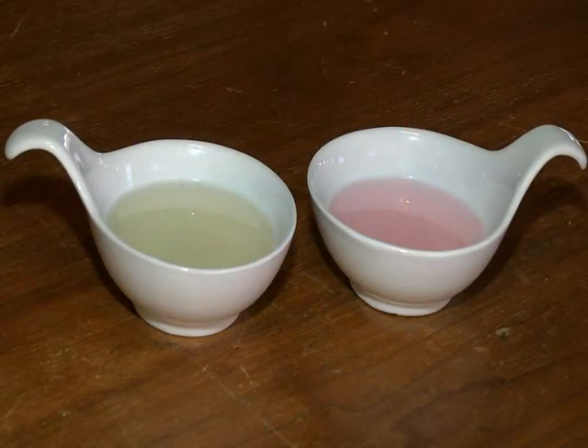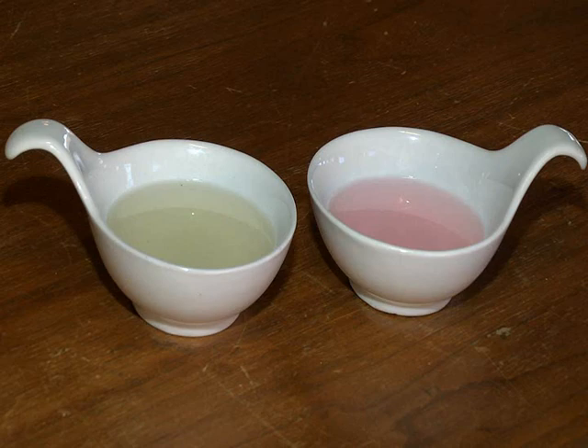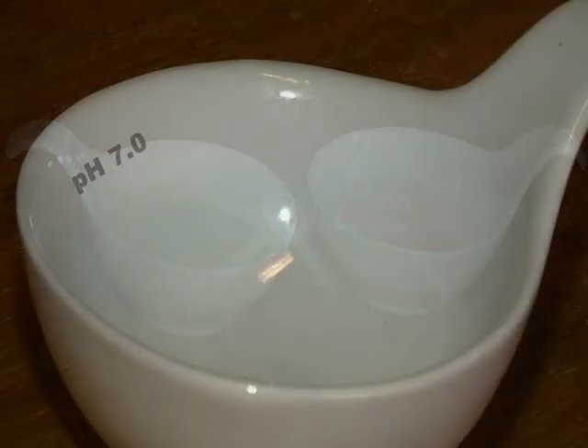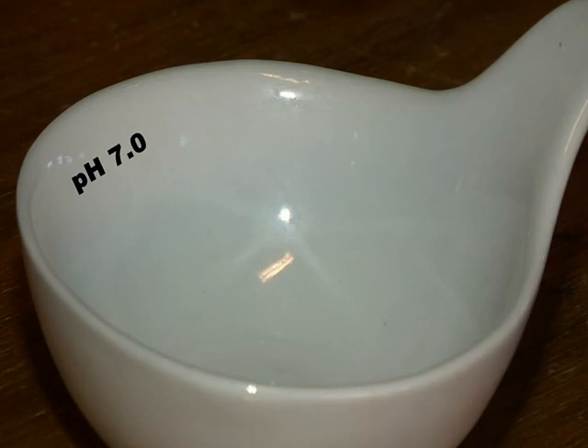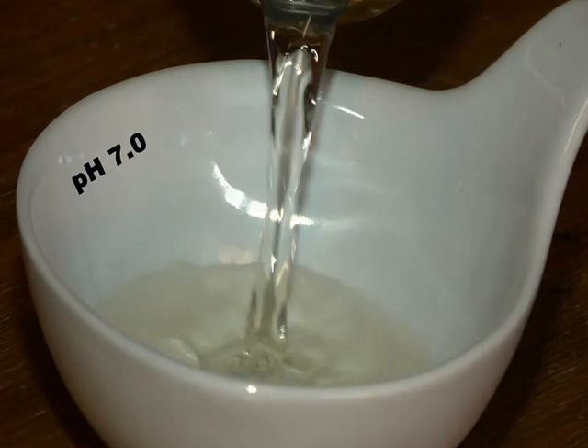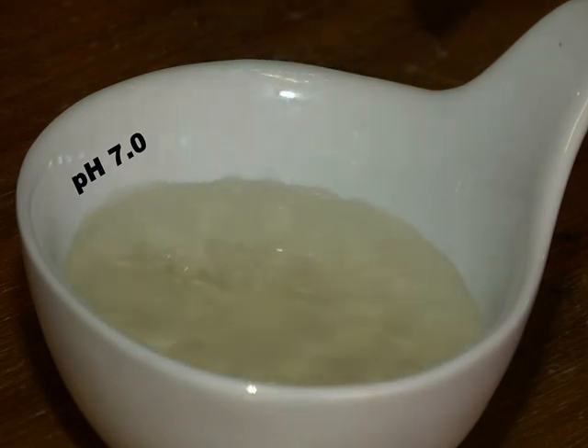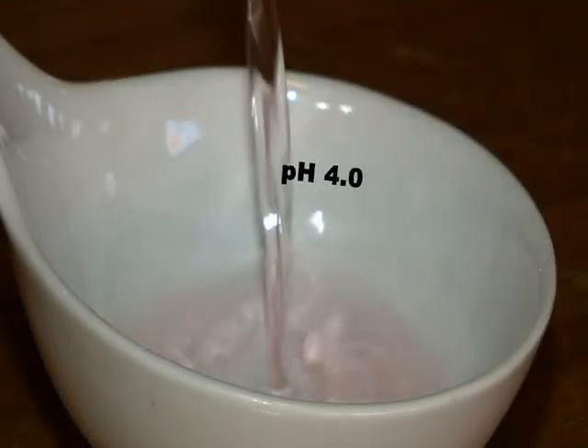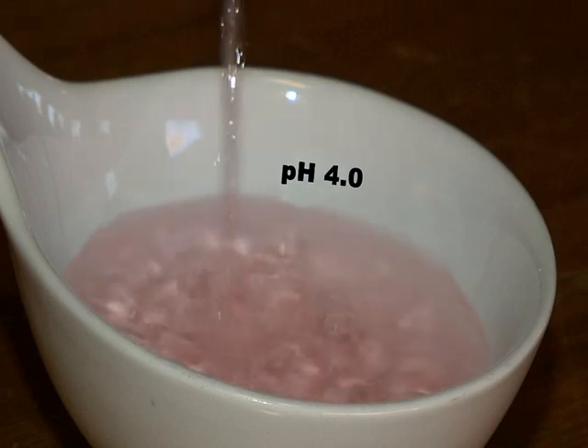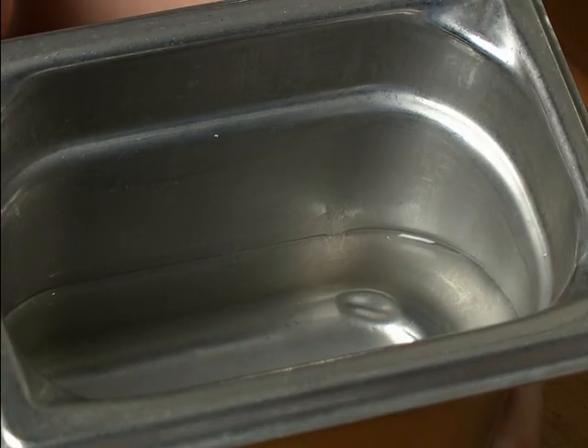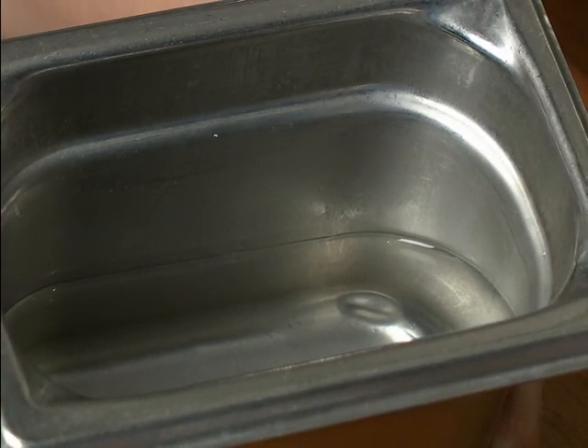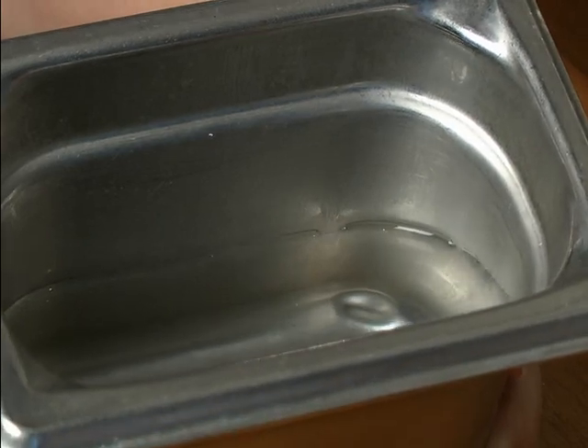Never use glass cups in a food preparation or processing area, since broken glass can get into the food. Proceed to fill 2 small plastic cups with colored buffers. One cup will contain pH 7.0 buffer and the other pH 4.0 buffer. Fill a plastic cup with pure distilled water. This is for rinsing the pH probe.